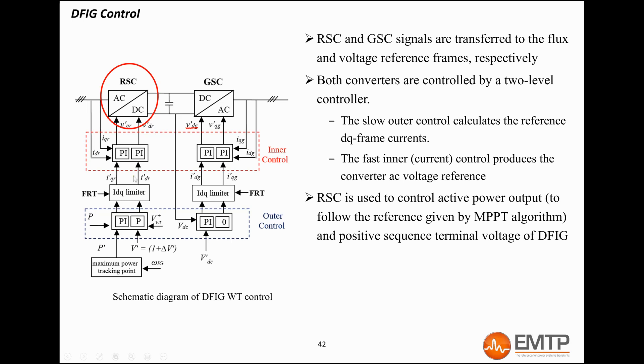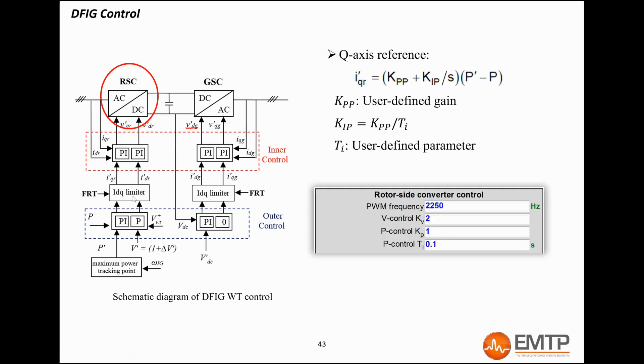The inner loop, which is the fastest one, produces the Q-axis voltage reference to follow the Q-axis current reference produced by the outer loop. Before being used by the inner loop, the current reference is limited by the IDQ limiter block, so the converter does not exceed its current capability, which could cause hardware damage. The limiter function will be explained later on in this presentation. The gains of the outer loop are calculated based on user-defined parameters, as shown here. The typical time constant of this loop is 0.1 seconds.